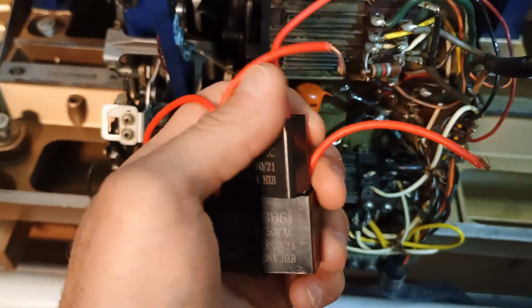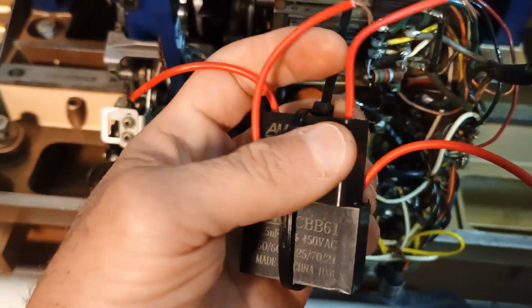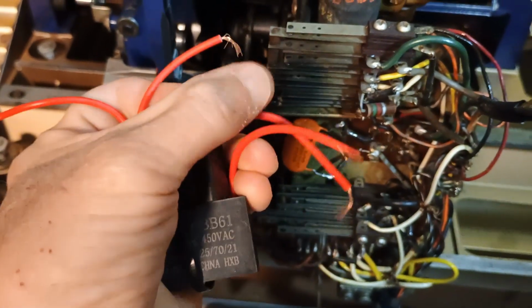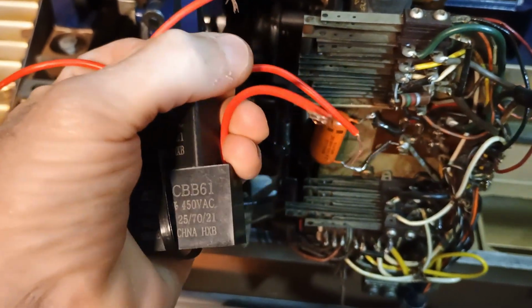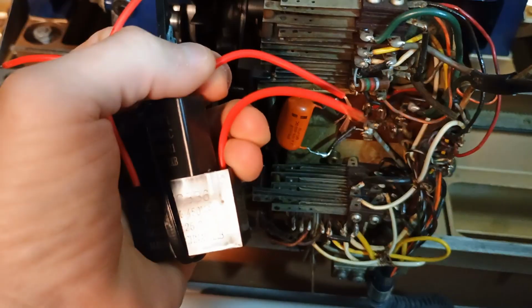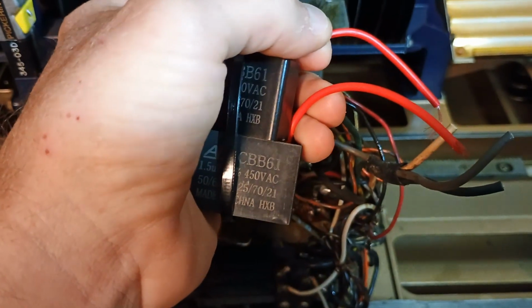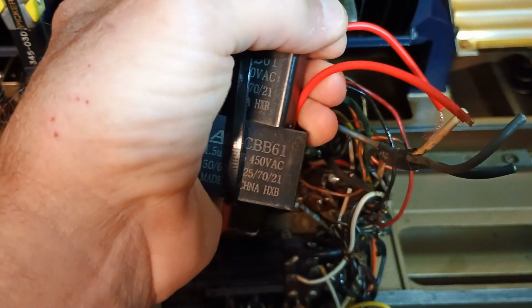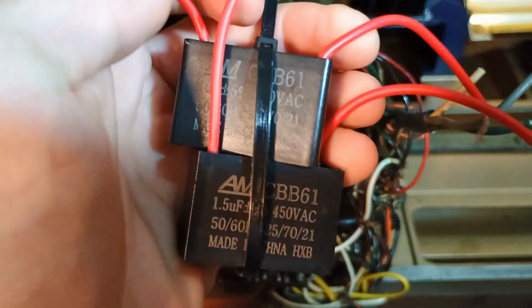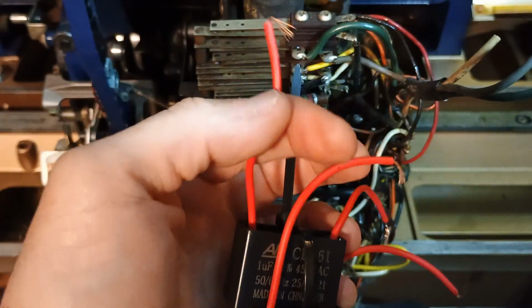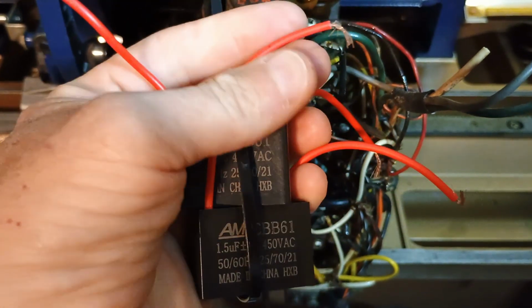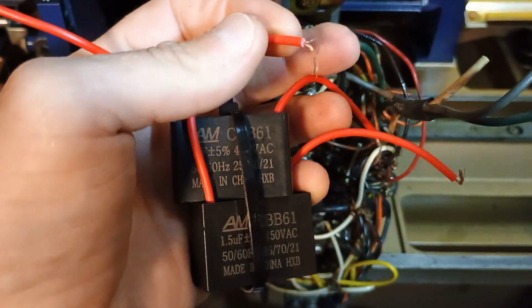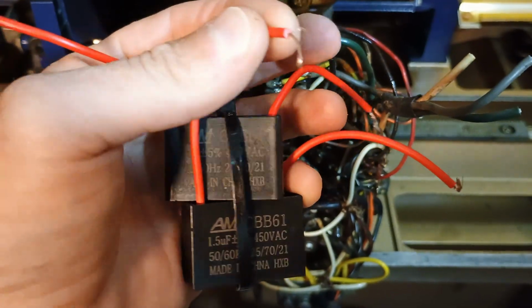All you're going to do is connect one side of each capacitor together - for example, connect these two together - then connect this to the white lead that you had coming out from the original capacitor. That's going to be your common right there. Then you'll connect the 1 microfarad to the correct wire, and on the other capacitor, which will be the 1.5, you'll connect that to the remaining lead.